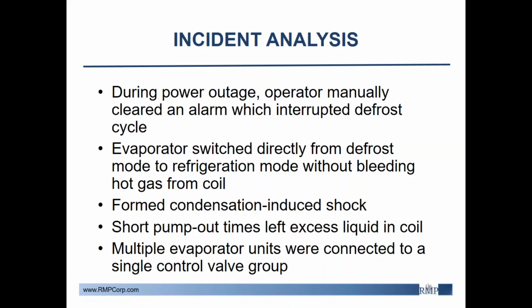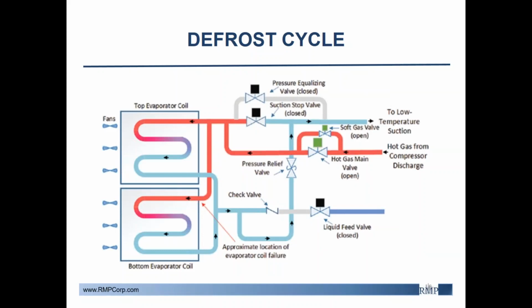The shocks ruptured the evaporator piping manifold and low-temperature suction piping on the roof. The problem went undetected because the defrost system is programmed not to allow liquid to enter the evaporator until the coil is depressurized. Therefore, if there were a problem, the operators would have been alerted. However, in this case, manual intervention caused a deviation from the normal sequence, overriding the system's normal programming.